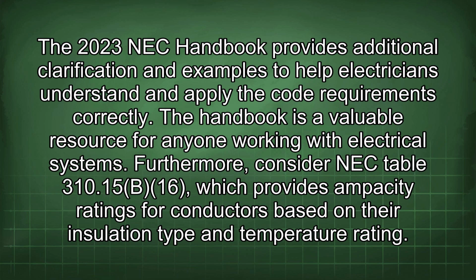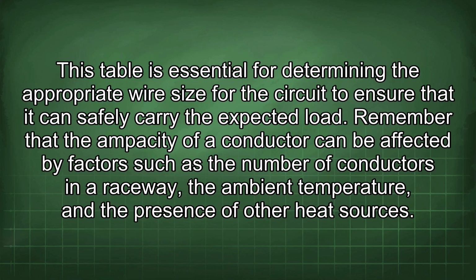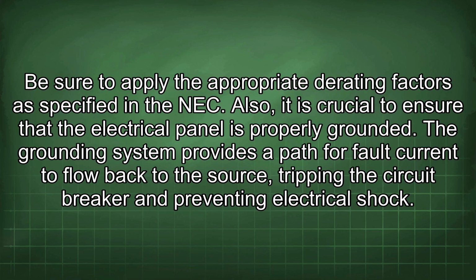Furthermore, consider NEC Table 310.15(B)(16), which provides ampacity ratings for conductors based on their insulation type and temperature rating. This table is essential for determining the appropriate wire size for the circuit to ensure that it can safely carry the expected load. Remember that the ampacity of a conductor can be affected by factors such as the number of conductors in a raceway, the ambient temperature, and the presence of other heat sources. Be sure to apply the appropriate derating factors as specified in the NEC.